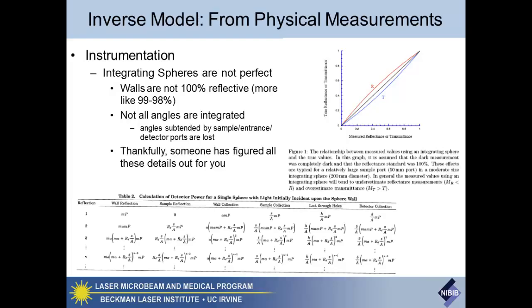Thankfully, people have thought about this problem for a long time and came up with a way of describing what will happen to photons after multiple reflections within the sphere, accounting for the fact that it's not a perfect 4π steradian integrator and that the reflectivity of the wall is not perfect. They went through and did the long, hard calculations and committed it to code so we don't have to look at that again — but be aware that it exists.